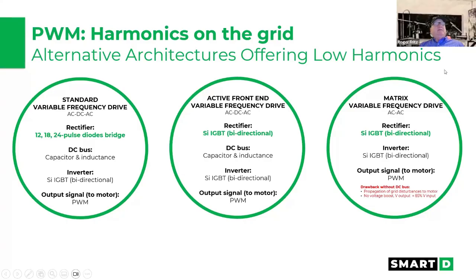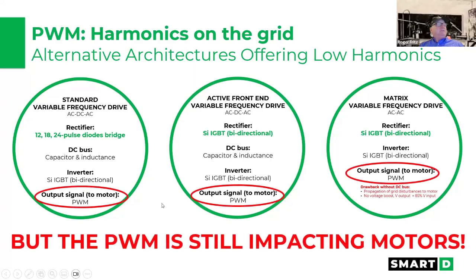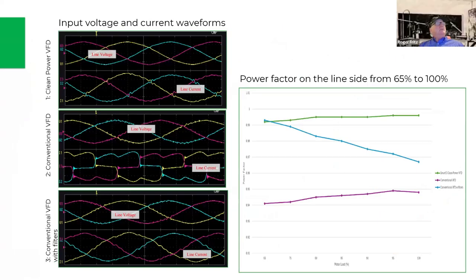There's also been a matrix drive design which has been out there, which also then feeds back. The disadvantage of that is it does drop the input voltage down to about 85%. So it ends up sucking a lot of the power off, and the total efficiency isn't as high as on other architectures. And it still has the impact that happens out there on the electric motors. So the motors still end up seeing that harmonic content. So you can see here the different options.